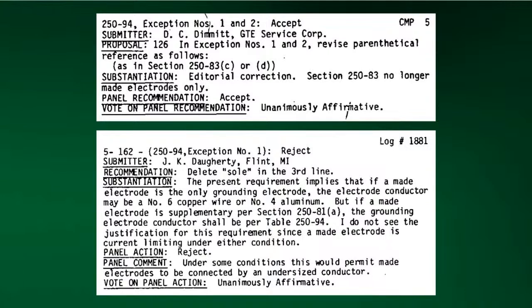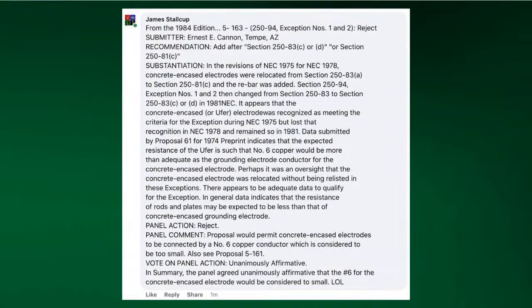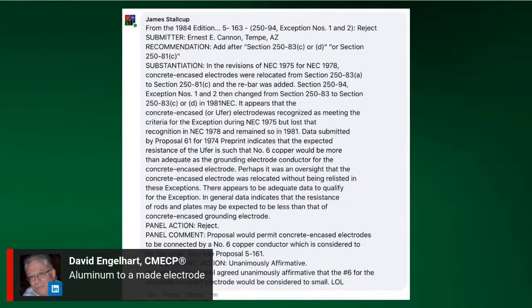And they said, due to the reason, under some conditions, this will permit made electrodes to be connected by what? An undersized conductor. Yep. So you got like a 100 amp panel board back that time. You could have actually done that and went to a what? Number 8. They are not going to allow that. So that's why they're telling you here, under some conditions, this could happen. So even if I go to the supplementary grounding electrode, they're telling you here that you still had to run over number 6 to it. Okay? Now, let's take a step further. Yeah, and David has a good point too. That could have had something to do with that too, but this is going to clear it right here.